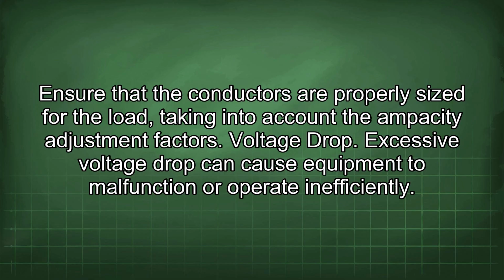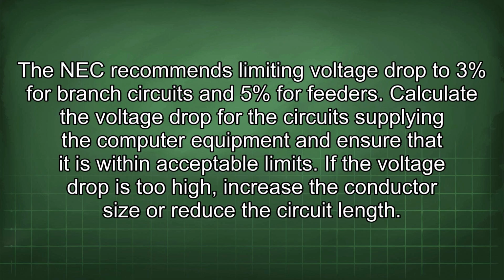Voltage drop. Excessive voltage drop can cause equipment to malfunction or operate inefficiently. The NEC recommends limiting voltage drop to 3% for branch circuits and 5% for feeders. Calculate the voltage drop for the circuit supplying the computer equipment and ensure that it is within acceptable limits. If the voltage drop is too high, increase the conductor size or reduce the circuit length.